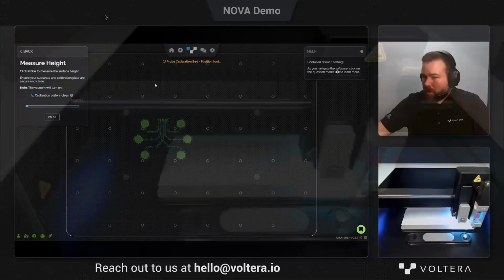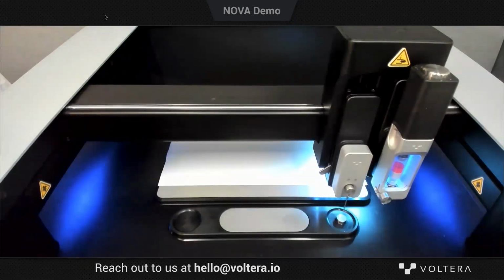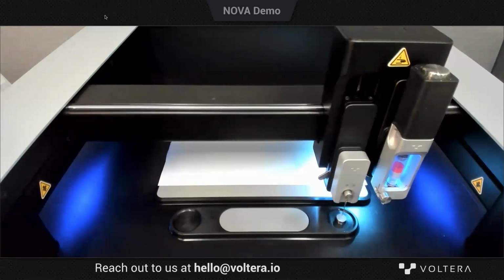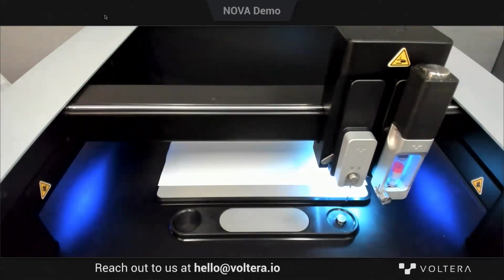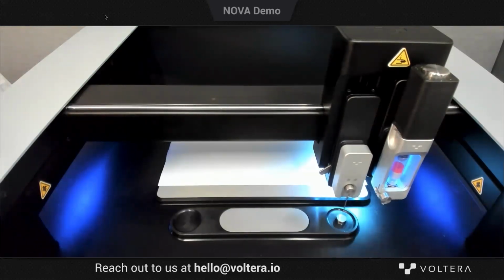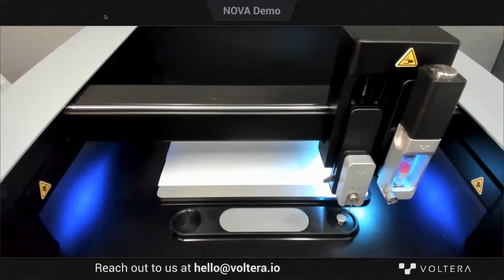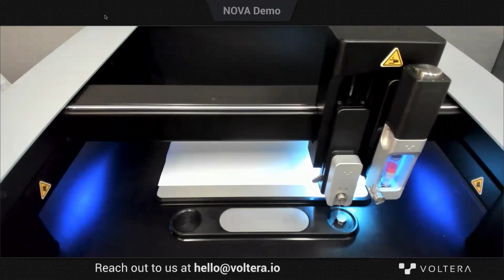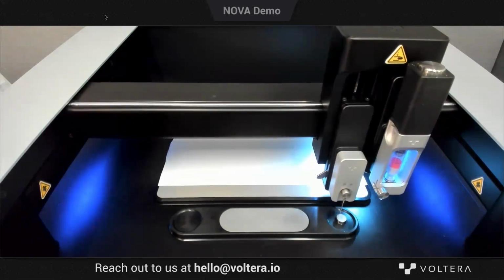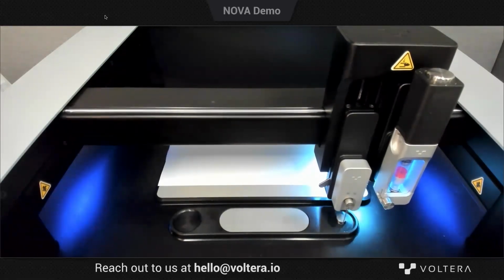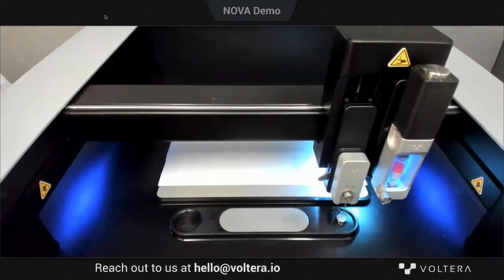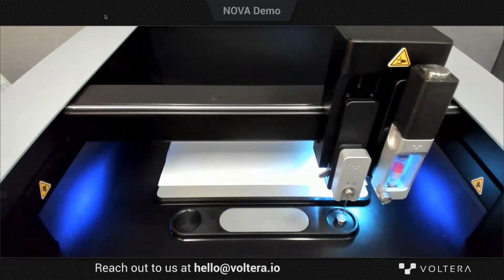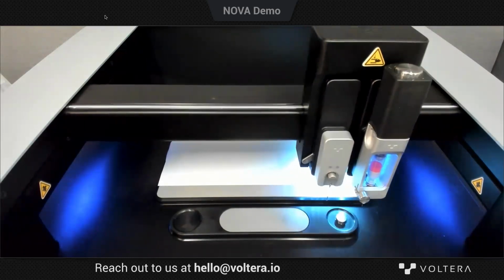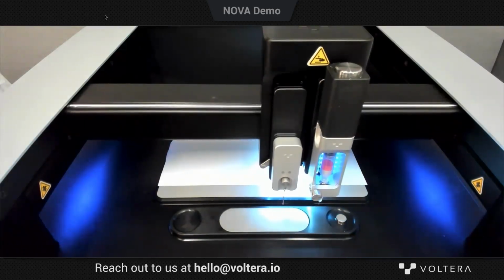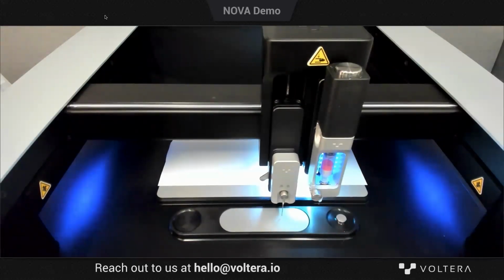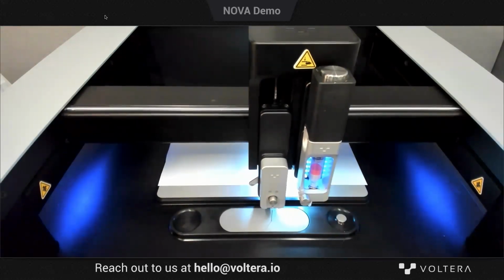While we're probing here, you can see Nova is going to be checking the probe with the XYZ positioner tool. This is so we can get the precise position of the probe in our 3D space, so in our X, our Y, and our Z axis. You can see it went down and touched the middle of the probe first. That was to get its Z height. And then it's touching on either side, in a north, south, east, west kind of direction. That's how we find the center of the tool in the X-axis and the center of the tool in the Y-axis. Once that's registered, we can move over to the calibration plate and start probing.